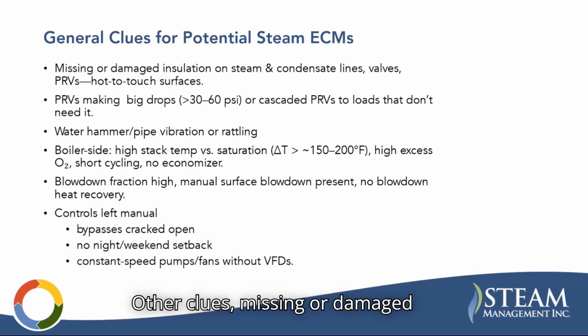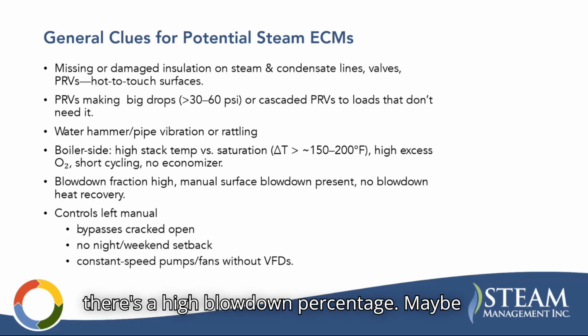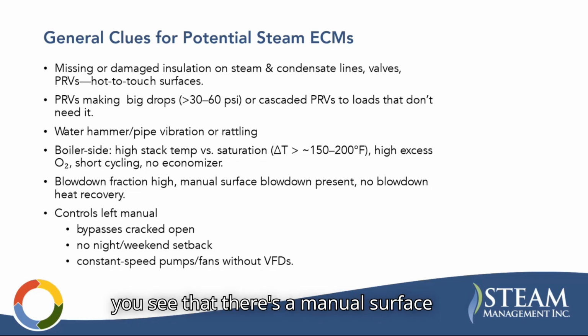Other clues: missing or damaged insulation, PRVs making big drops or cascading PRVs. If there's indication of water hammer, piping vibration, rattling, high stack temperatures, high excess air, a lot of short cycling in the boiler. There's no economizer. Again, we talked about blowdown, so there's a high blowdown percentage. Maybe you see a manual surface blowdown present and no blowdown heat recovery system. That could be an opportunity. Also, another general indicator is if the controls are left manual, so you have bypasses cracked open, there's no night setback, and pumps are on constant speed motors.